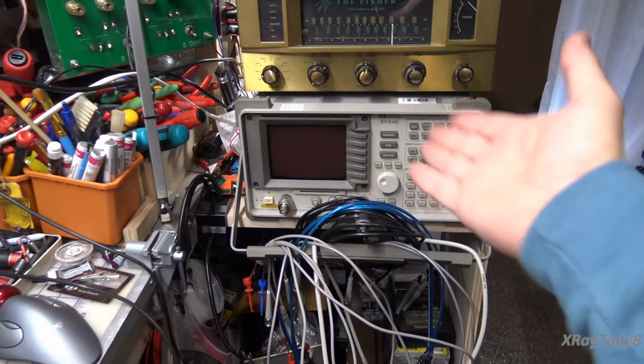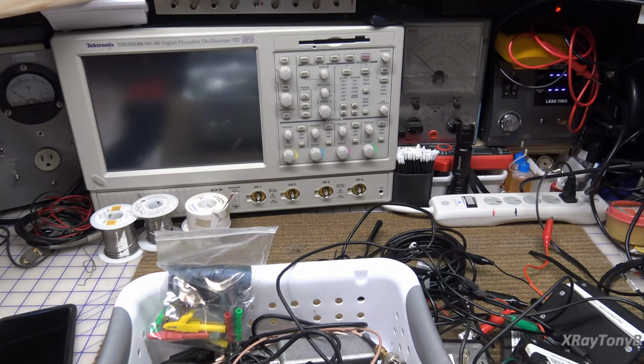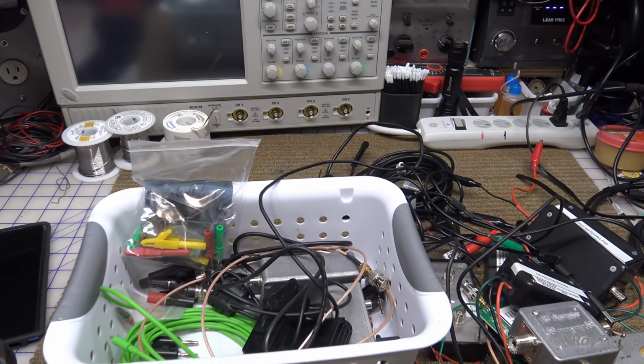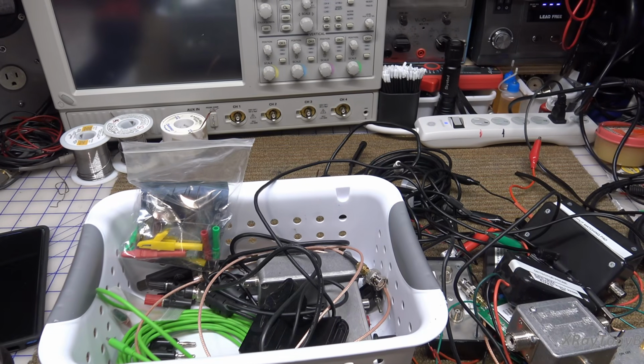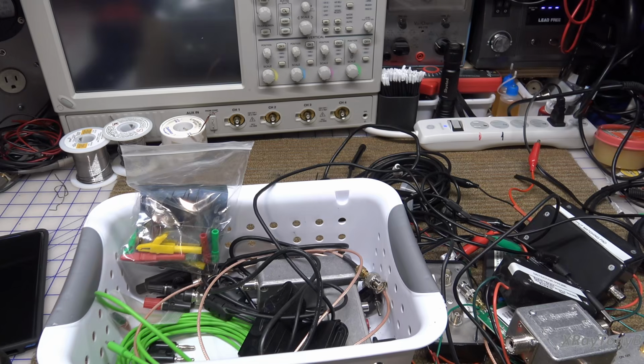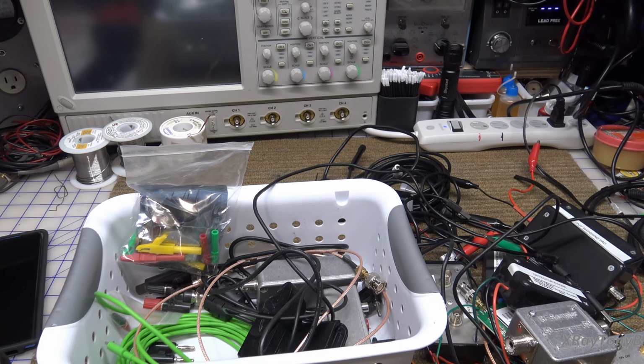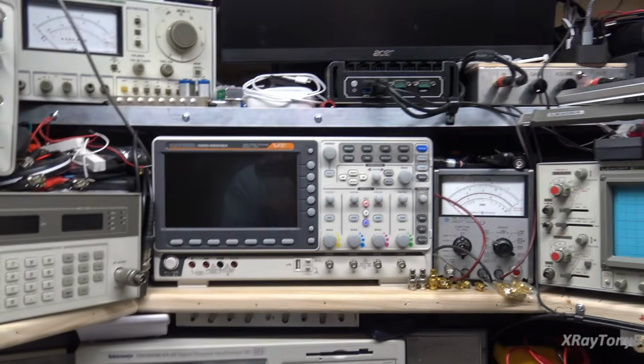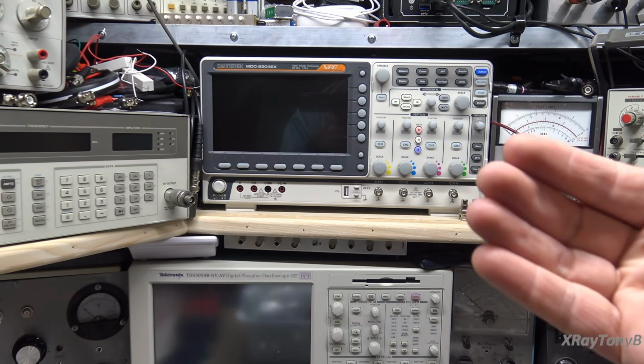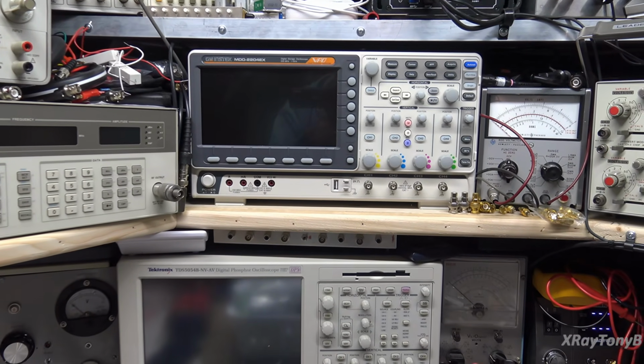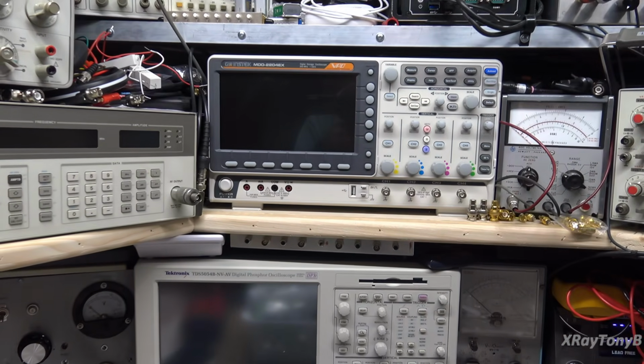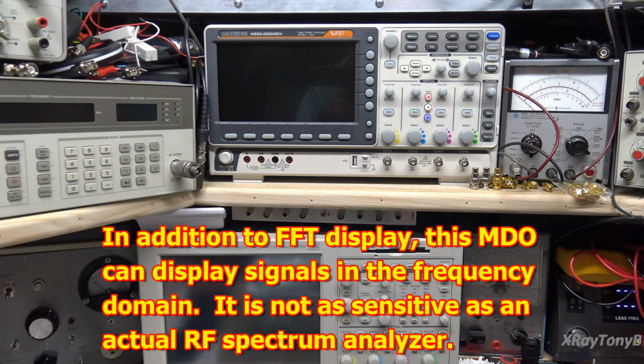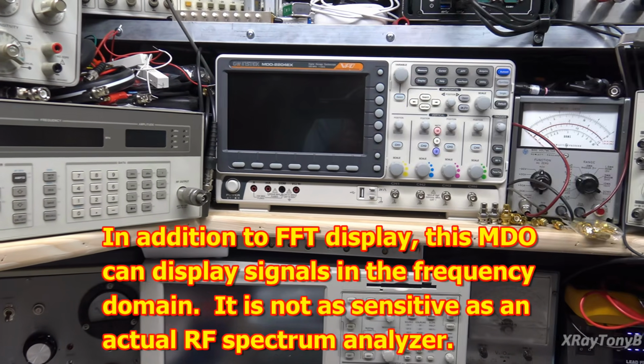But with a normal spectrum analyzer like this MDO here, or with an actual spectrum analyzer, you can't look at anything usually lower than like 9 kilohertz, or sometimes higher than that. And a normal spectrum analyzer is just not very accurate at that range, nor can it take the higher input levels that you might be getting from speaker terminals or so forth. So it makes it very difficult to use a traditional spectrum analyzer. Now, this GW Instek up here, since it's not a real spectrum analyzer, it's kind of a software one. It uses the oscilloscope circuitry, and then it does some math tricks, and it's not FFT, but it actually will show you a poor man's spectrum analyzer, let's call it. But it will go down to audio frequency. Most of them will not.